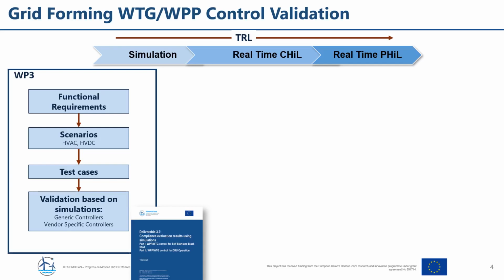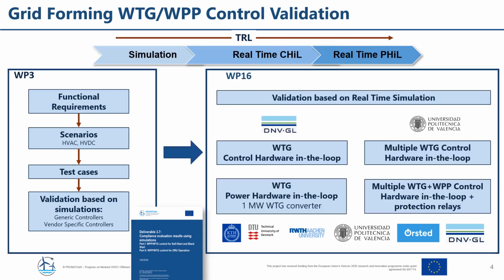Our main aim has been to increase the TRL of the grid-forming controllers. In the initial work packages 2 and 3, we defined the functional requirements for such controllers, the scenarios, both for HVDC and HVAC connected wind farms, the test cases, and finally we carried out the validation of different controllers by means of detailed simulations. Once we finished with the validation using simulations, we moved into work package 16, where we carried out the validation based on real-time simulations.